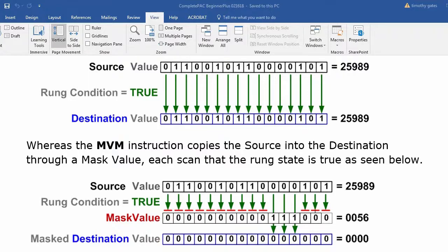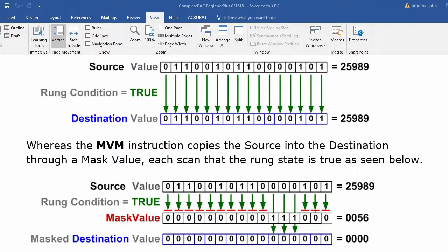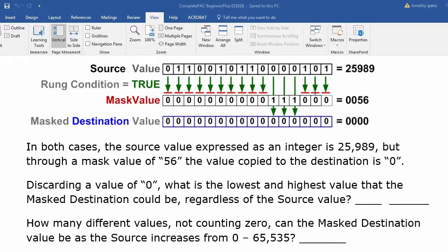This little scheme allows you to have seven trays going through your system, and each one of them has a unique bolt pattern that gets read when it first breaks the beam of photo eye one as it enters onto this conveyor. Now remember, we are working with the move instruction, specifically the move with mask. So in the upper illustration, you're moving, which is a word copy, you're copying the source to the destination. The upper illustration would be a regular move instruction moving the bit pattern that represents decimal 25,989 from the source to the destination. Whereas the bottom illustration is a mask move. The move is actually masked.